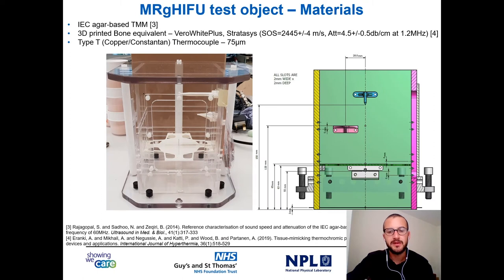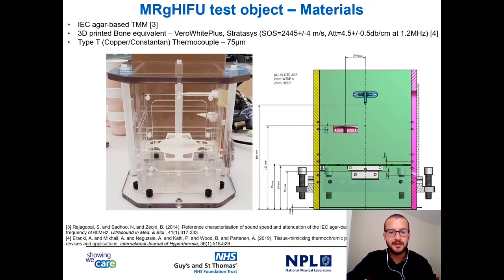When you want to build the phantom, the first problem is the choice of materials. Materials have to be compatible with the technology of interest, which in this case are ultrasound and magnetic resonance imaging. We use the well-known IEC recipe, which is an agar-based TMM, with speed of sound of 1540 m/s and attenuation of 0.5 dB per centimeter. We use 3D-printed bone equivalent discs to mimic flat bone, and type-T copper-constantan thermocouples of size 75 micron, to be MRI compatible and to minimize interaction with ultrasound fields.